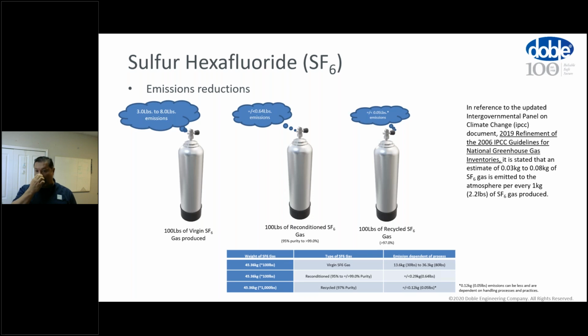And this information, by the way, you can find in the 2019 refinement of the IPCC guidelines. They just came out this year with 2022, and it doesn't create any changes to what was mentioned in 2019, but it's a lot of reading. I believe it's over 250 something pages, but nonetheless, the 2019 addressed this really well, and I think that's an important thing to consider when using or relying on virgin SF6. Reconditioned and recycled SF6 gas, the 3 R's, by testing and seeing that the gas meets the targets of what you need, the specifications, you could easily reuse SF6 gas in the field.